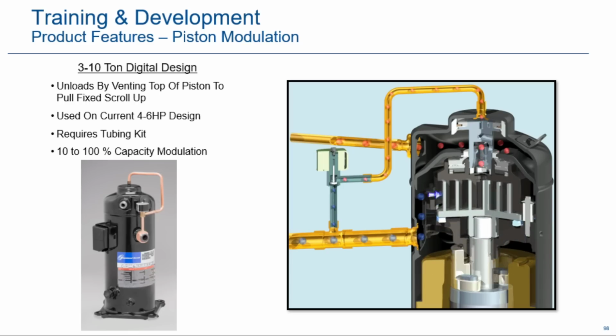So one tip: if you go up to a compressor and it's a digital and you put your amp clamp on it and you're wondering why it's making so much noise, when it's loaded it's going to be, say as an example, 15 amps. When it unloads, it's going to be 9 amps. So if it keeps doing that, you know it's a digital. A fixed compressor is not going to do that. So that's one tip on that.